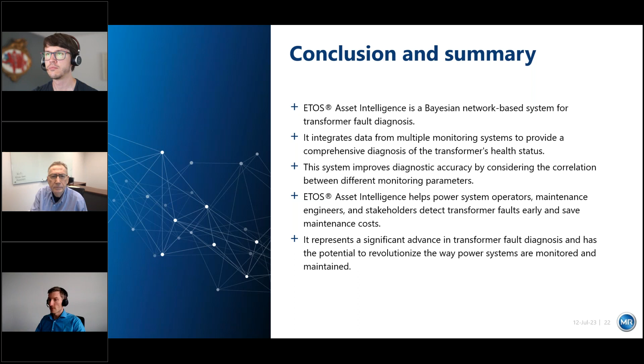With 'open' we don't mean it's open to hack, because cybersecurity is very important to us. But it was on purpose to not show any brand names, because customers like different brands and different sensors, and it works with all sensors. Of course, if you have better information about the reliability of those sensors, we expect our sensors to have a certain reliability programmed into the Bayesian network. If this differs from the sensor that's connected, it might change the probabilities of the diagnostics a little bit, but I'm pretty sure most sensors work pretty well on transformers, and we can use the exact same numbers for third-party sensors too. So the answer is a clear yes.